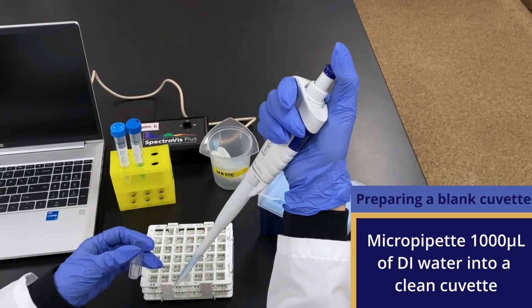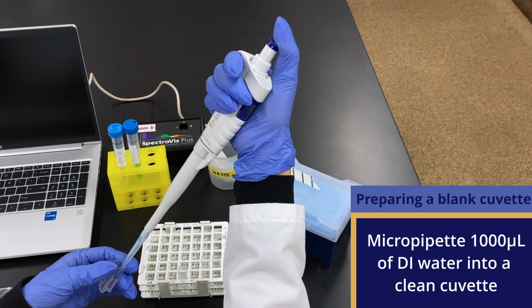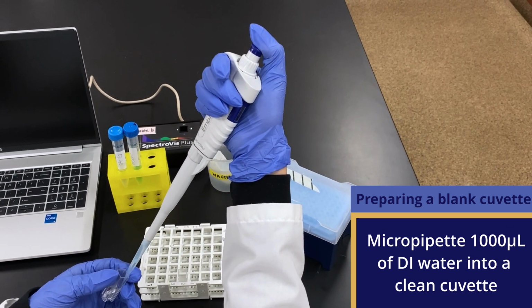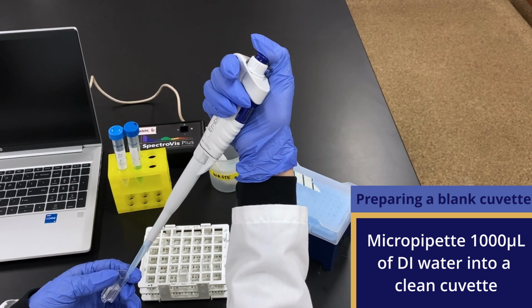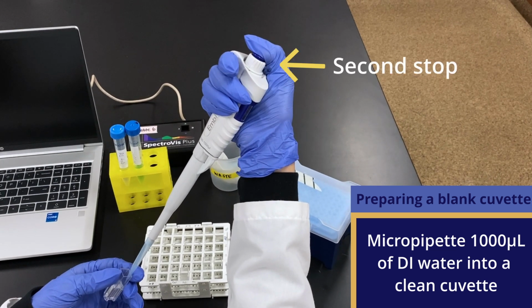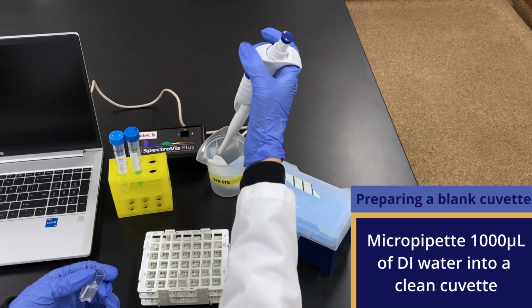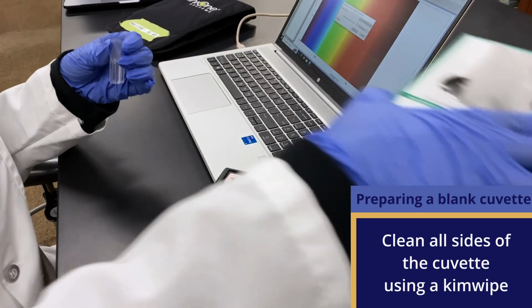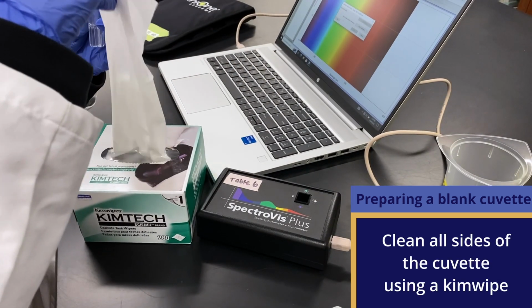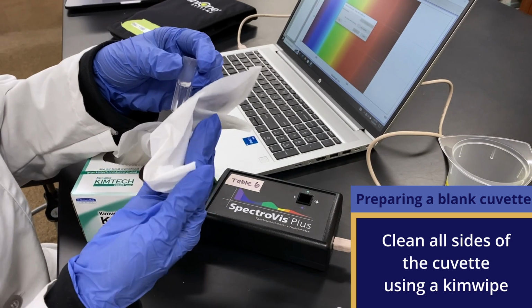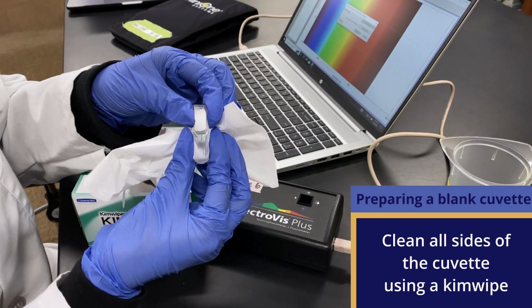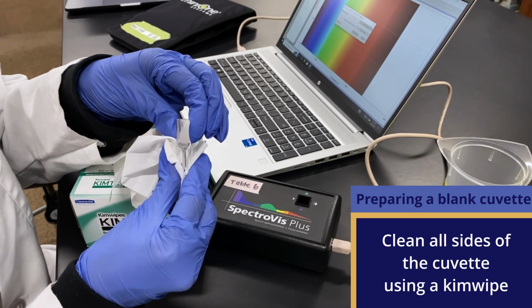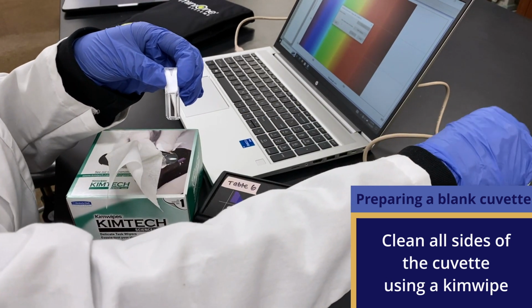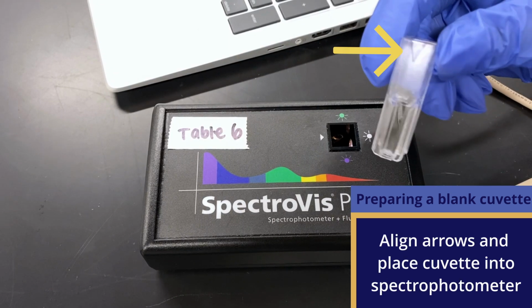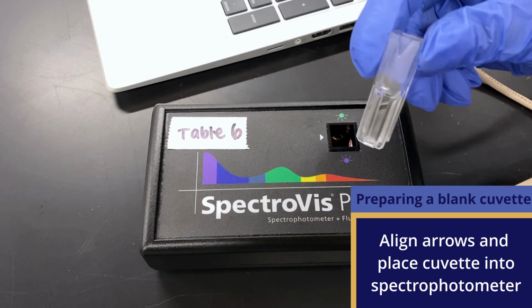Then dispense the water by touching the pipette tip to the side of the cuvette to prevent splashing. Press down to the second stop when dispensing to ensure all liquid is expelled. Use a Kim wipe to clean the cuvette's exterior to avoid any obstructions in the spectrophotometer's light path. Identify the arrow on the cuvette and align it with the arrow on the spectrophotometer before placing it in the device.